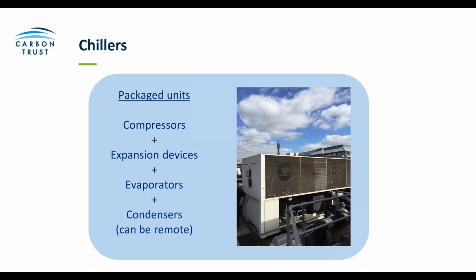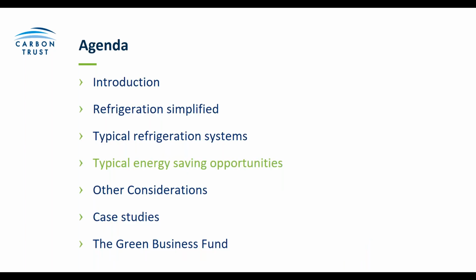Typically, these chillers are chosen to meet a maximum cooling load during the very warmest of weather. However, for most of the time, so 99% of the time, the chiller probably won't be running at these conditions. So the load will probably be smaller or the weather cooler, and this presents opportunities for energy saving, which we'll hopefully get onto a little bit later. So that's a look at refrigeration in its very kind of basic form.